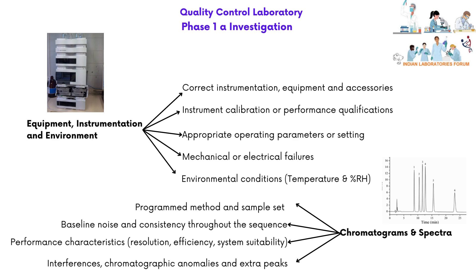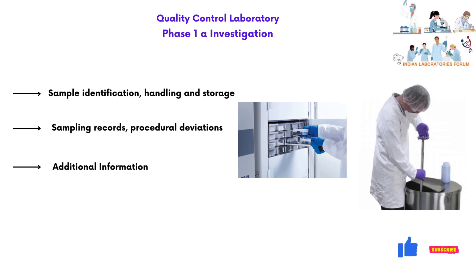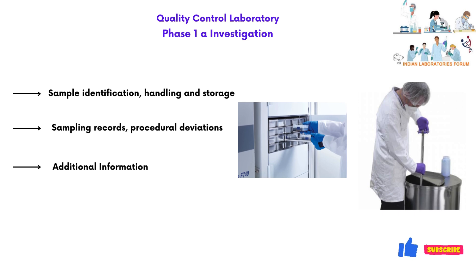Review of chromatograms and spectra includes: programmed method and sample set, baseline noise and consistency throughout the sequence, review of performance characteristics such as resolution, efficiency, and system suitability, review of interferences, chromatographic anomalies, and extra peaks. Review of sample identification, handling and storage conditions, review of sampling records and procedural deviations, and any other data review for additional information about root cause.